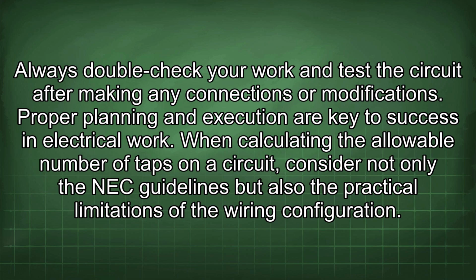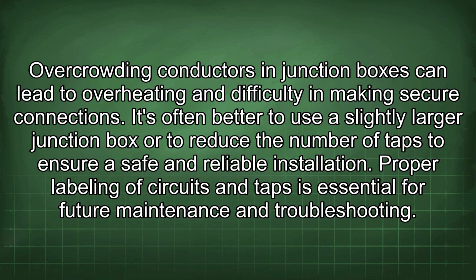When calculating the allowable number of taps on a circuit, consider not only the NEC guidelines but also the practical limitations of the wiring configuration. Overcrowding conductors in junction boxes can lead to overheating and difficulty in making secure connections. It's often better to use a slightly larger junction box or to reduce the number of taps to ensure a safe and reliable installation. Proper labeling of circuits and taps is essential for future maintenance and troubleshooting.